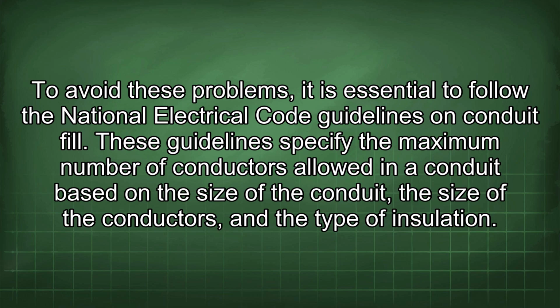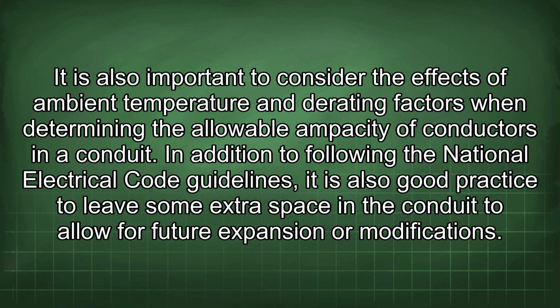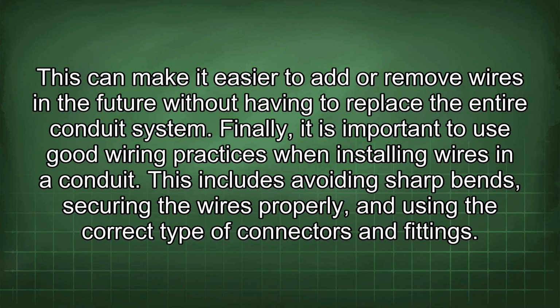These guidelines specify the maximum number of conductors allowed in a conduit based on the size of the conduit, the size of the conductors, and the type of insulation. It is also important to consider the effects of ambient temperature and derating factors when determining the allowable ampacity of conductors in a conduit. In addition to following the National Electrical Code guidelines, it is also good practice to leave some extra space in the conduit to allow for future expansion or modifications. This can make it easier to add or remove wires in the future without having to replace the entire conduit system.